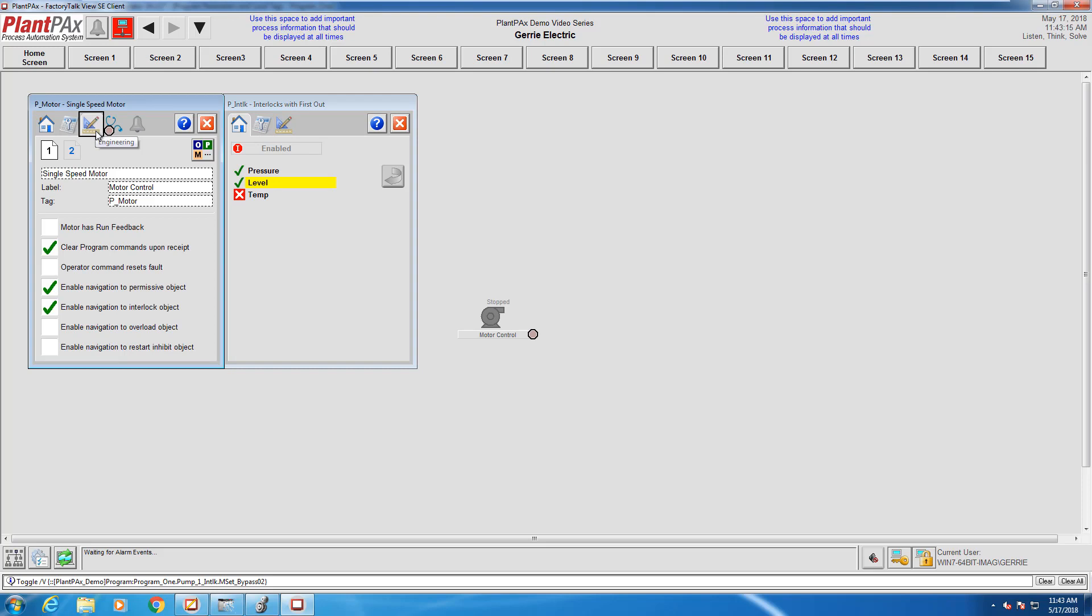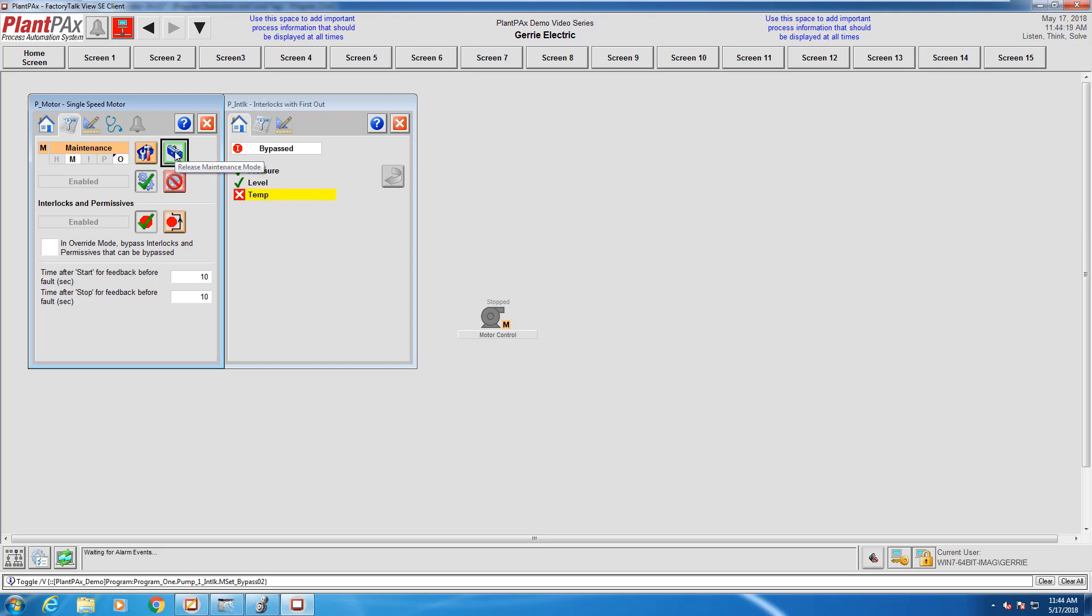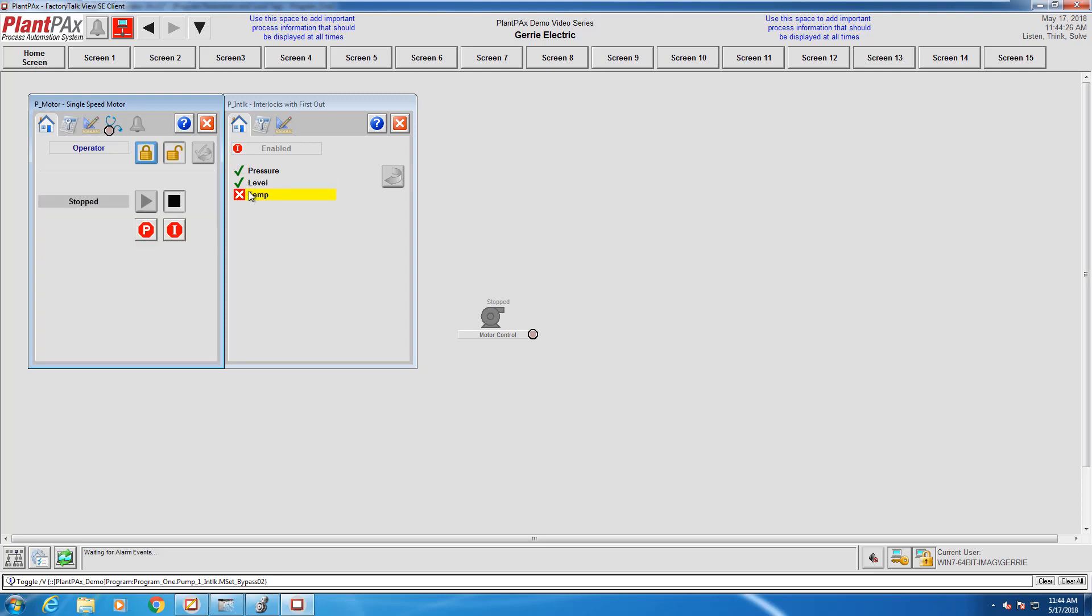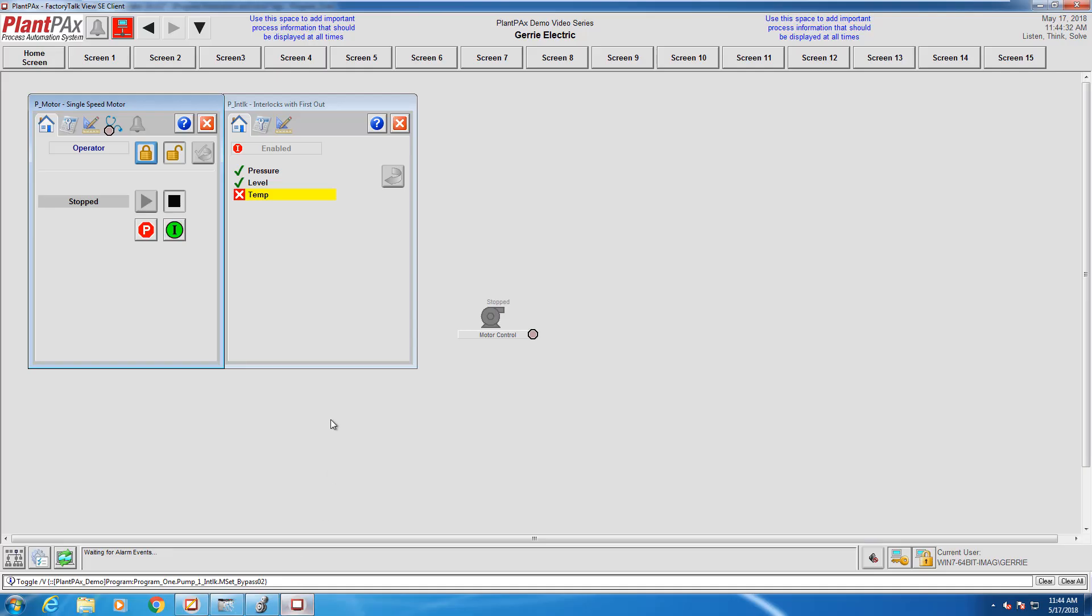We're clicking on maintenance mode and we enter maintenance mode, and the interlock is bypassed, allowing us to start the motor. I can get out of maintenance mode by clicking on this closed toolbox right here, and I'm going to head back into my PLC and change the state of temp so that the interlock is allowing the motor to run. You'll see when we head back over the interlock is green and is no longer preventing the motor from running.